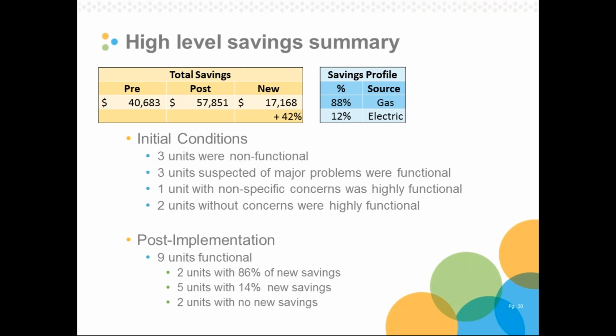Let's look at some of the individual units. Very broadly, we had 3 units that were non-functioning. 33% of the units that we encountered in this study were not recovering energy when we found them. On the other hand, we found 3 units that were suspected of not running or suspected of major problems, and they were working basically fine. We had 1 unit that had very non-specific concerns, and we found that it was working great, in fact. And then our 2 units that we hoped were running great, there were no specific concerns, and they did serve as good examples of well-implemented ERVs. They were highly functional and optimized units. After we left, we were lucky in that we had 9 functional energy recovery units.